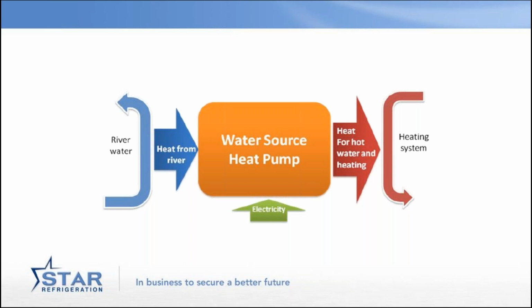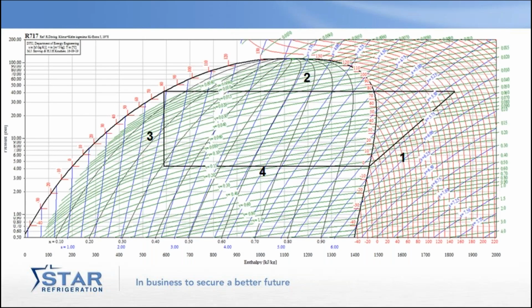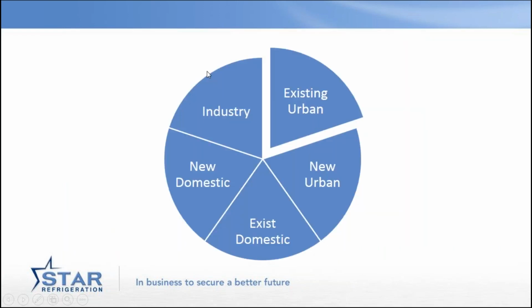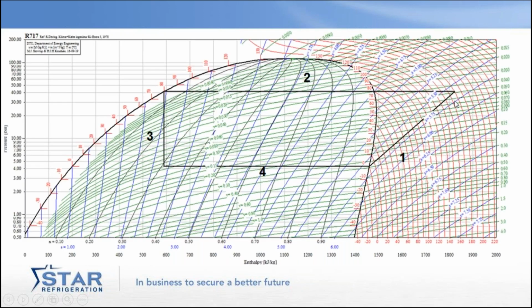What I'm going to hopefully take you through today is what makes the difference between an average heat pump and a good heat pump. They're all governed by the physics. As Scotty in Star Trek said, you can't change the laws of physics, and maybe he sounds a wee bit like me. But this is the pH diagram, and basically the amount of heat out we get is line number two across the top, and the amount of electricity we put in is line number one, and 2 - 1 should equal 4. I know that's funny maths, but the amount of heat that we are taking in from the water or the air is across the bottom.